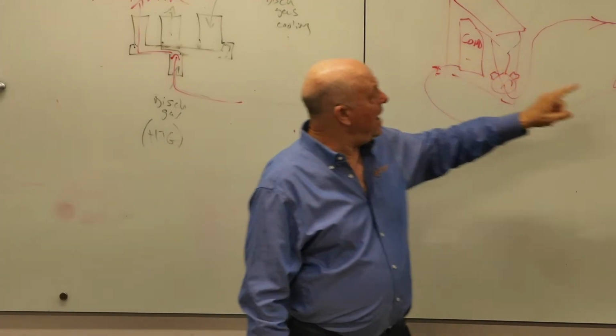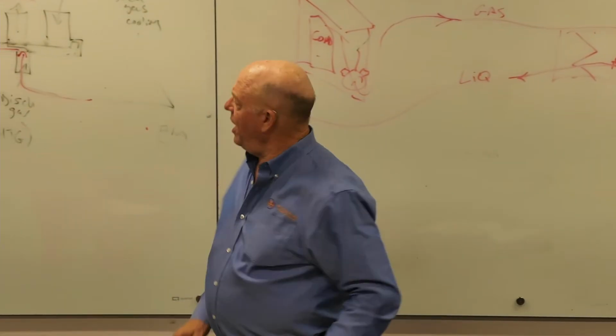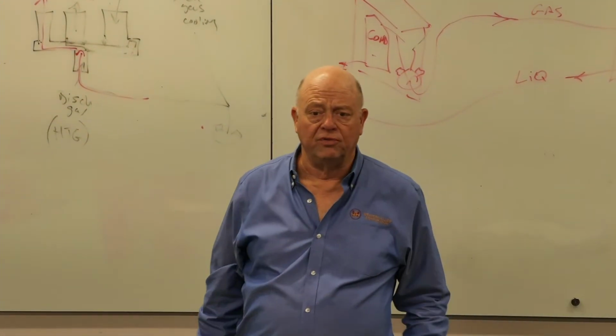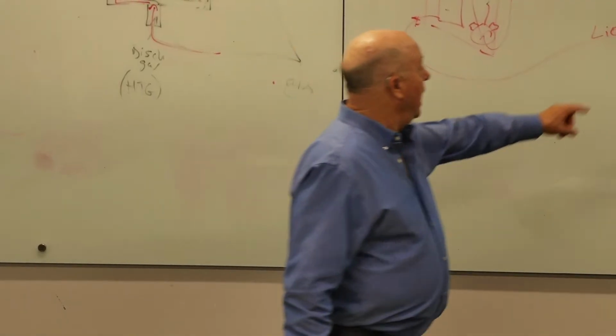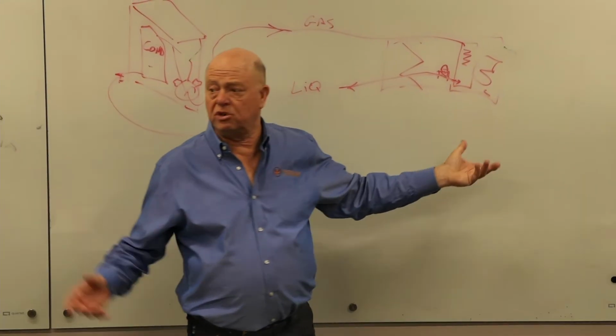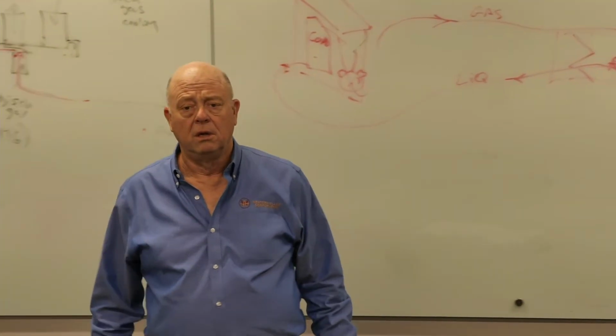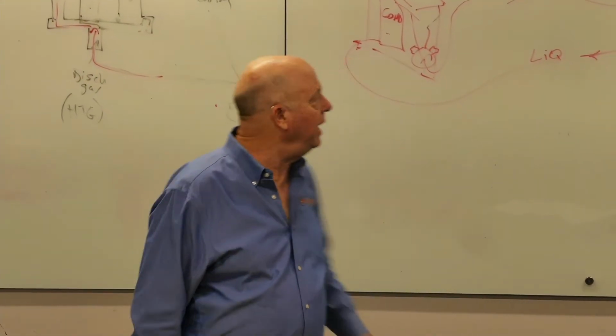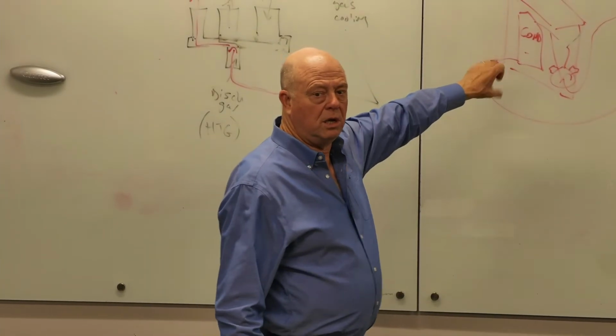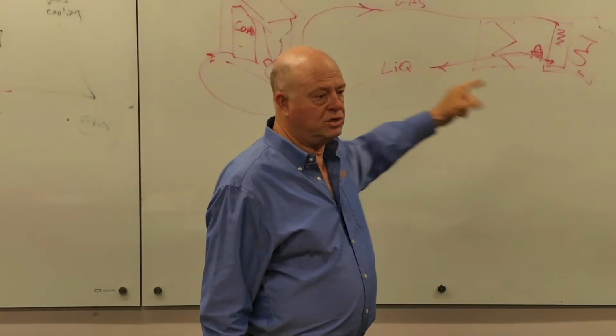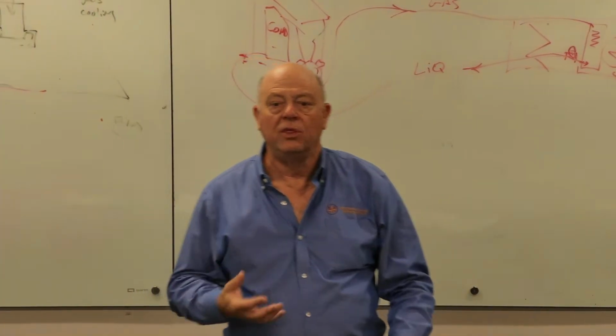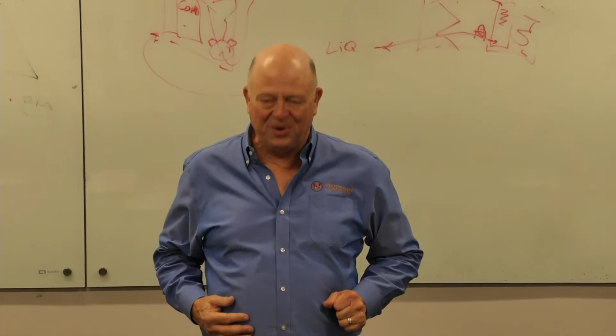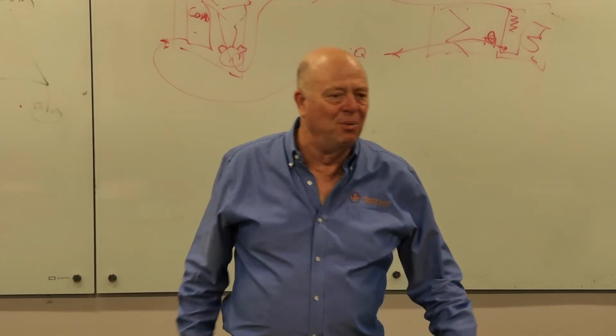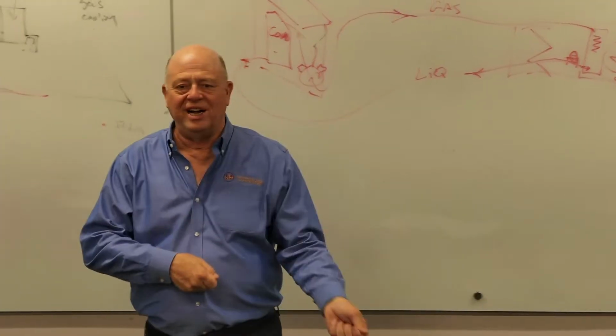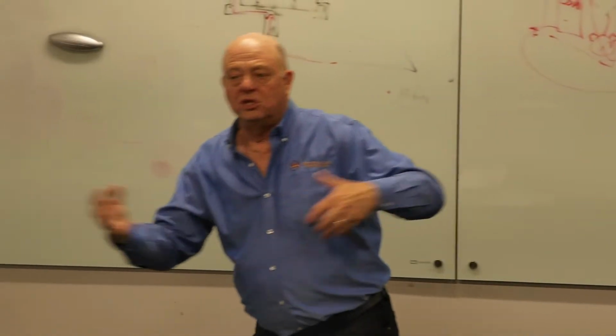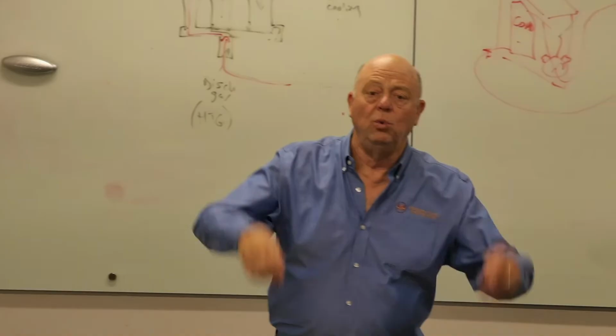But these have to be matched. And if you have a condensing unit that's had its second compressor failure and it's 22 years old, and this air handler's fine, right? I mean, the drain pan's not rusted through, it's working great. You can't simply buy a new condensing unit and hook it to that old air handler, because the coils are nowhere near matched. The refrigerant charge would be correct for one or the other, summer or winter. Which do you want? And what are you going to do, adjust the refrigerant charge every time? Because if you don't, that subcooling superheat thing will get all out of whack and you will start feeding liquid to your compressor.